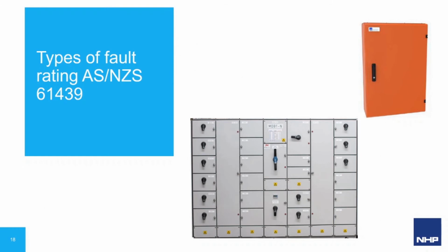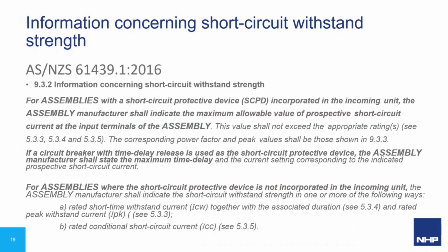Now that we understand the requirements, we will have a look at the type of rating that is stipulated in AS 61439. Part 1, Section 9.3.2 tells us the information concerning short circuit withstand strength and how we should communicate this information. Depending on whether or not there is a short circuit protection device and the location of the protection device, this will influence the rating that we give our assembly.